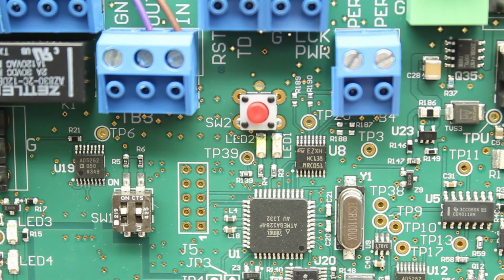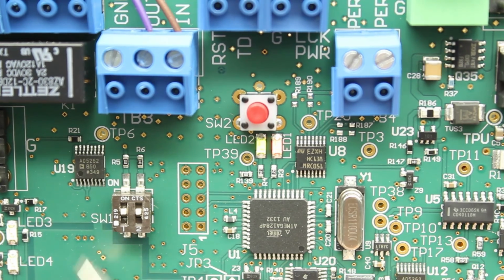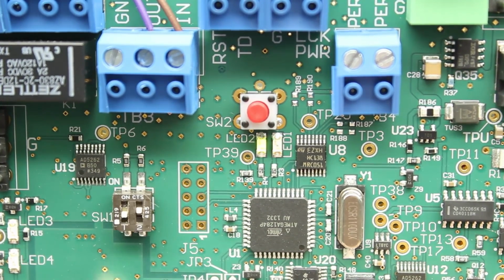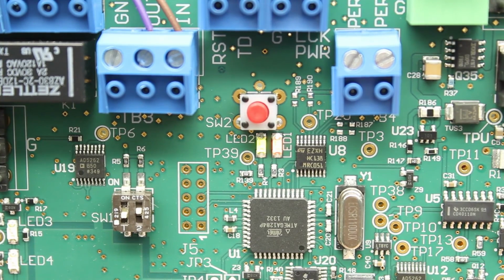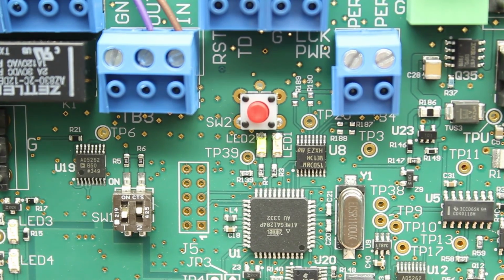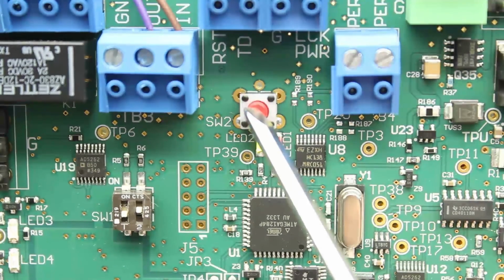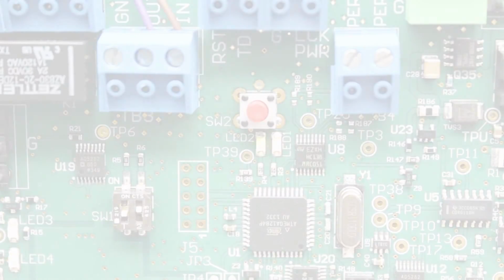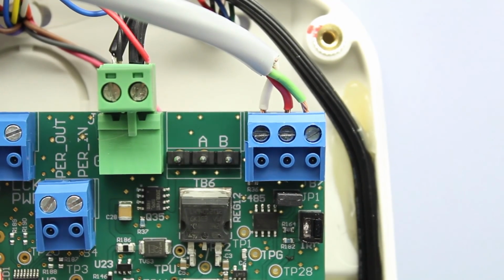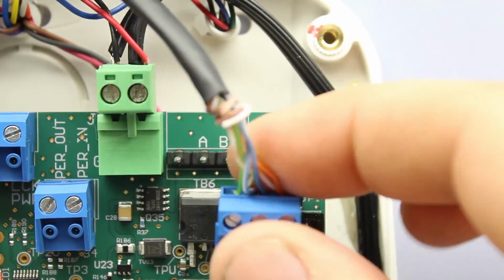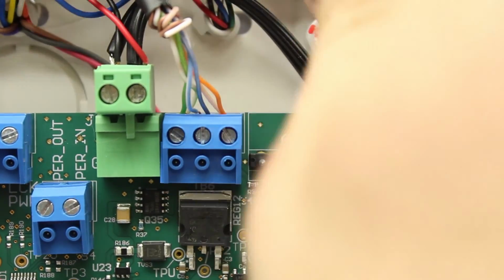Once configuration is complete, the door controller must be returned to the run mode. Set the switches on SW1 so that switch 1 is in the down position and 2 is in the up position. Cycle power to the unit by pressing the red reset switch. Reconnect the Tek-CARE 700 network with TB6 and TB7. Replace the cover, and the door controller is now ready for use.